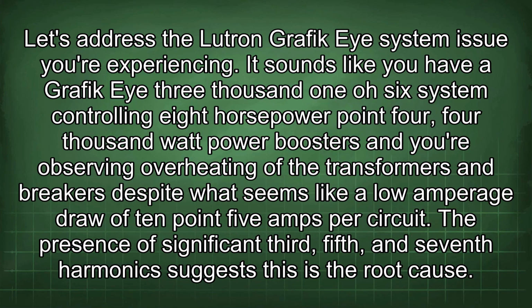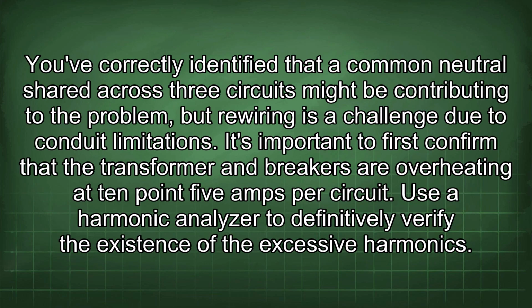Let's address the Lutron Grafik Eye system issue you're experiencing. It sounds like you have a Grafik Eye 3106 system controlling 8 horsepower, 4000 watt power boosters, and you're observing overheating of the transformers and breakers despite what seems like a low amperage draw of 10.5 amps per circuit. The presence of significant third, fifth, and seventh harmonics suggests this is the root cause. You've correctly identified that a common neutral shared across 3 circuits might be contributing to the problem, but rewiring is a challenge due to conduit limitations.